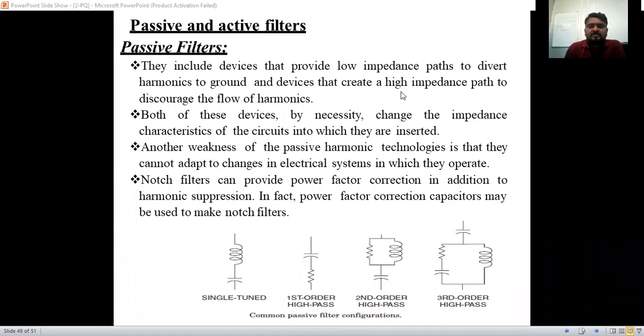So these filters are going to provide a low impedance path, which means the higher harmonic currents will divert into the ground where the filters are connected. By doing this, we are diverting or controlling the harmonics. The passive filters include devices that provide low impedance paths to divert harmonics to ground, and devices that create a high impedance path to discourage the flow of harmonics. By increasing the impedance, the higher harmonic currents are opposed.